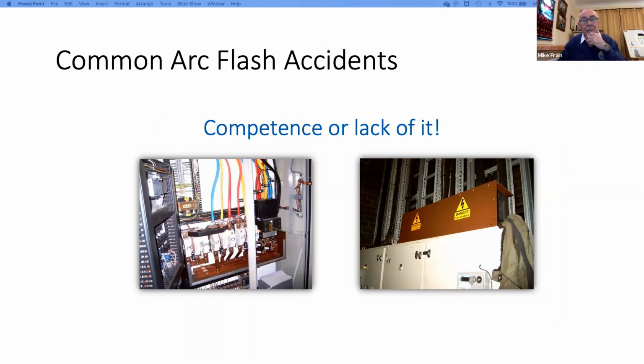Another one here, this is not an arc flash, but it could have been one. And I've seen so many instances where screening, phase shields and internal trunking lids have been missing in control panels. And that's why I sometimes yawn when people say we've designed out the hazard in the switchgear design, because this is what happens later on. People alter things and carry out unauthorized alterations. And in this particular case, it's a compressor mains panel, and you can see that there's 800 amp bus bars in the bottom there, and there was a lad working in there at the time, which attracted me over to it. And on further investigation, I found part of the shrouding had been left off, and it's actually on the adjacent panel. I think you can see it there. I had to search for it, but that's where it ended up.